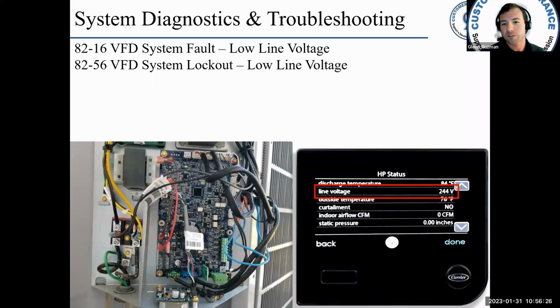8216 VFD system fault, low line voltage, and 8256 low line voltage lockout. Now, this is a little different. We talked earlier about the voltage that was read by the transformer on the secondary side. This line voltage fault is actually read by the VFD itself.